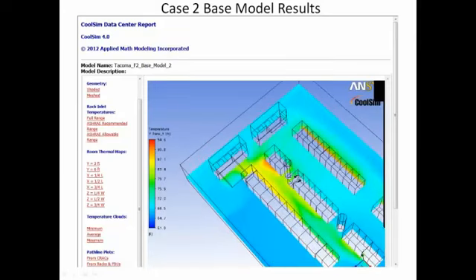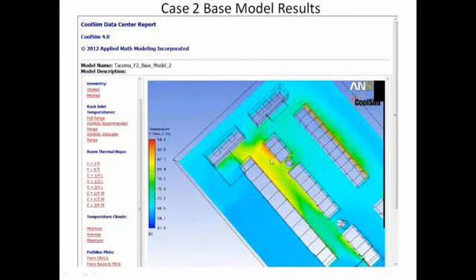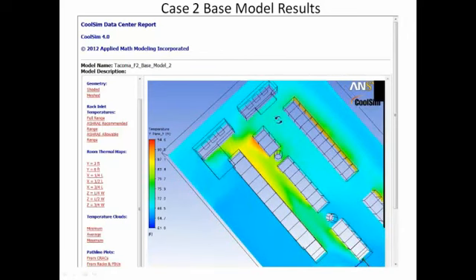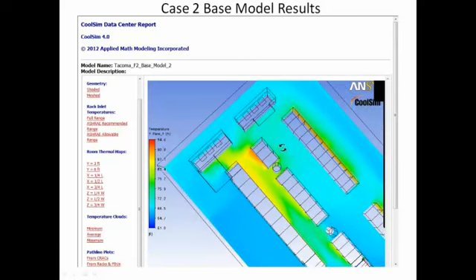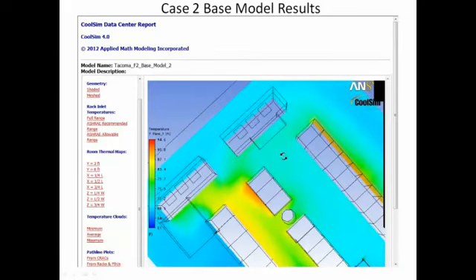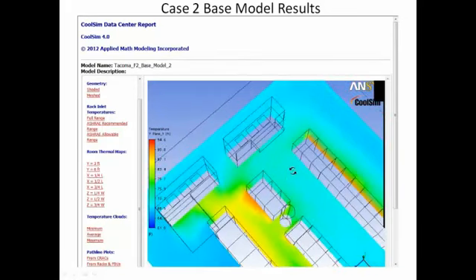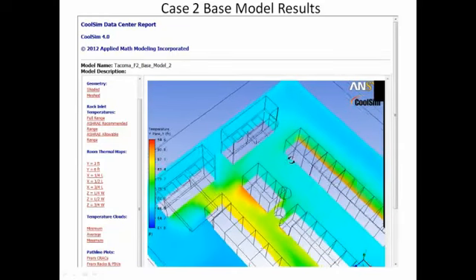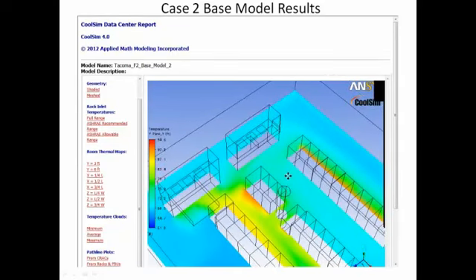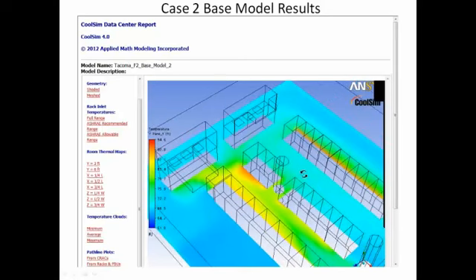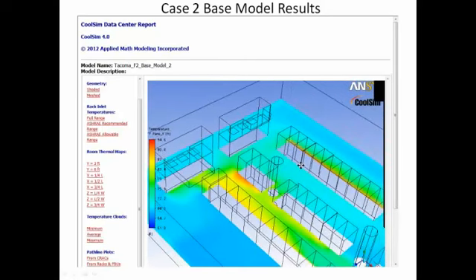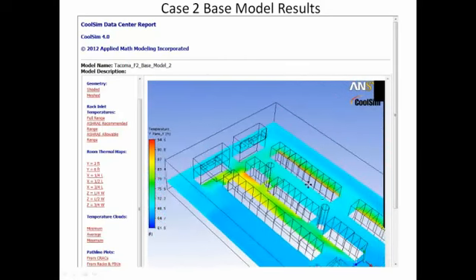So we don't have very good return. The return path here is too cold. This should be warmer right here because I'm 3 feet off the floor. And so my temperature variation on these racks is not that good. It's not as good as it could be. So this is, you know, yet another situation.